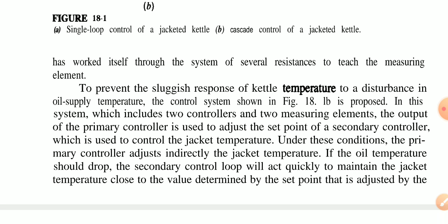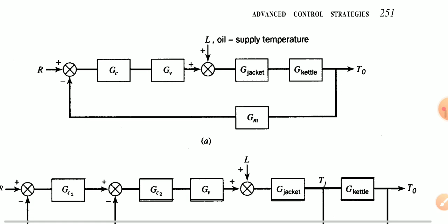Under this condition, the primary controller adjusts the jacket temperature indirectly. If the oil temperature should drop, the secondary control loop will act quickly to maintain the jacket temperature close to the value determined by the set point that is adjusted by the primary controller. This is the block diagram: advanced control strategies, a single loop conventional control system and a cascade control system.